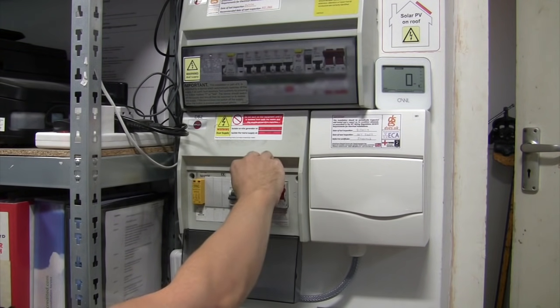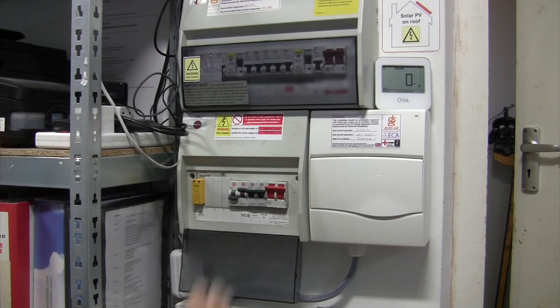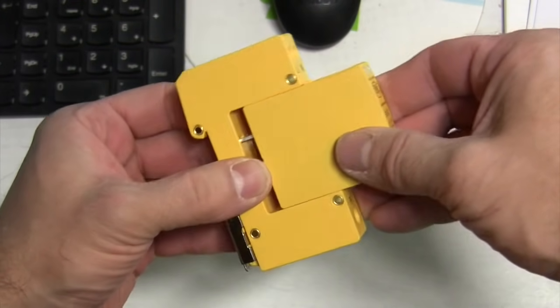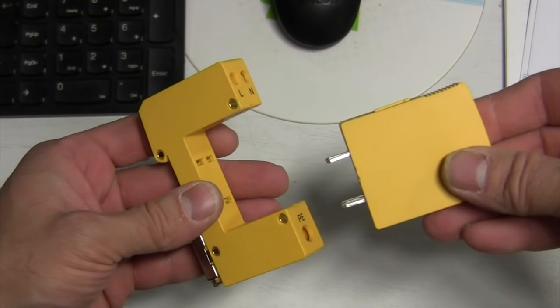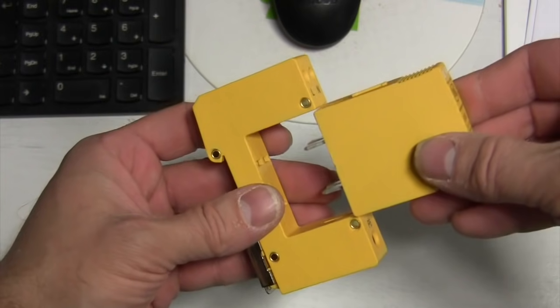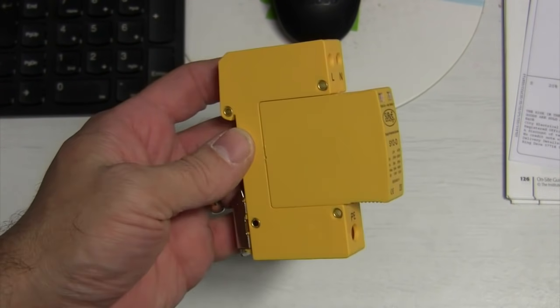That is, unless the surge was so great that the arse has been totally blown out of the thing, in which case the visual indicator should show red to inform you a replacement module is required. The surge module can itself be removed from the connection housing and a replacement unit slotted back into place, which hopefully saves time out on site.